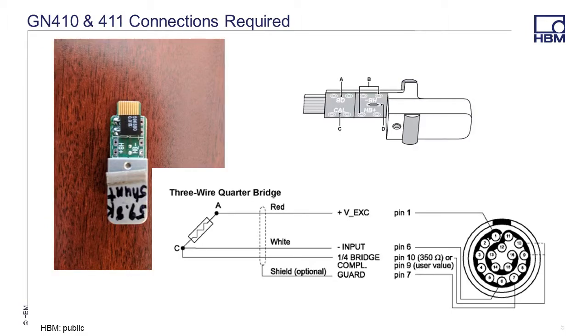To perform the shunt calibration, you will need to make some physical connections from the gauge back to the 16-pin Lemo connector on the GN410 and 411 card. Wiring in this connector is not easy and should not be attempted if you are not trained at soldering. However, if you can solder a strain gauge, you can solder this connector. Please see our other videos on soldering or strain gauge wiring if you would like a refresher.